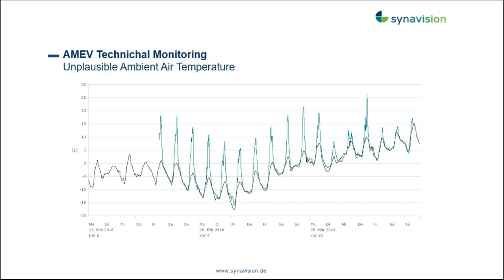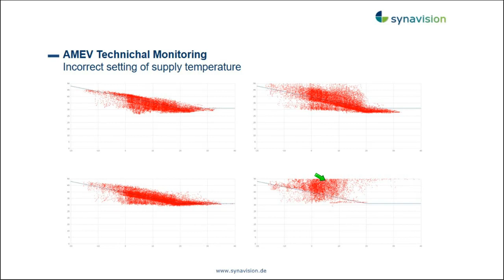Here's an example of heat pump supply temperature in residential multi-story buildings. The heat pumps of these 4 buildings supplied identical buildings - they should all look alike, with a characteristic where supply temperature goes up in winter, like here, higher, 35 to 40 degrees, and very low in summer. Unfortunately, in 2 buildings, the heat pumps supplied basically a mess of temperatures, going up to 50 degrees and more, and of course the coefficient of performance is very poor in those systems.